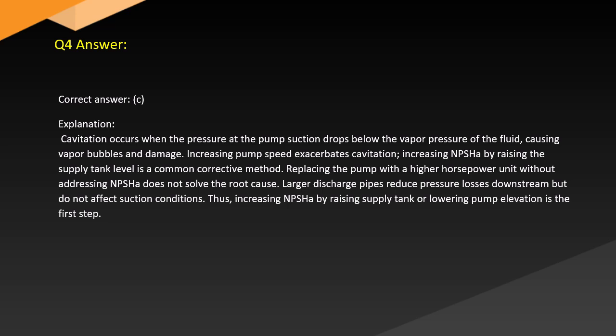Replacing the pump with a higher horsepower unit without addressing the suction conditions does not solve the root cause. Larger discharge pipes reduce pressure losses downstream, but do not affect suction conditions. Thus, increasing pressure by raising the supply tank or lowering the pump elevation is the first step.